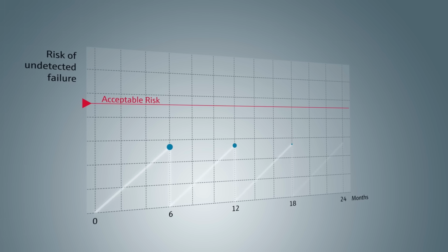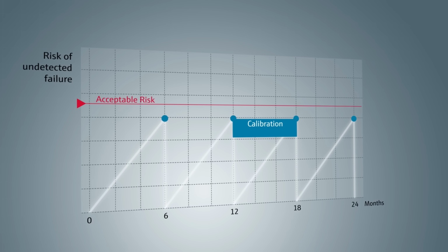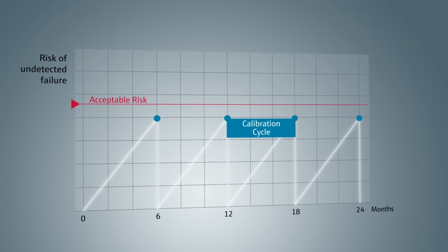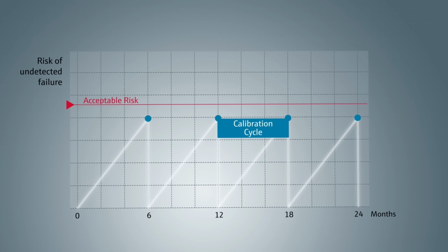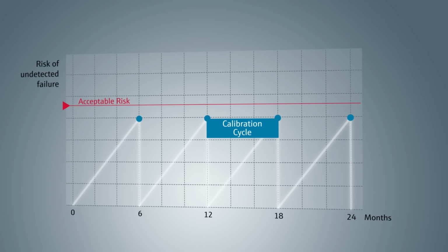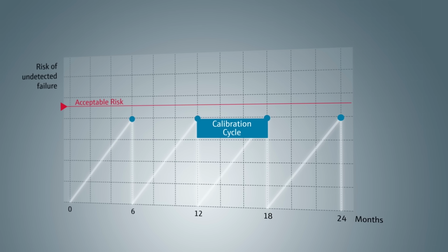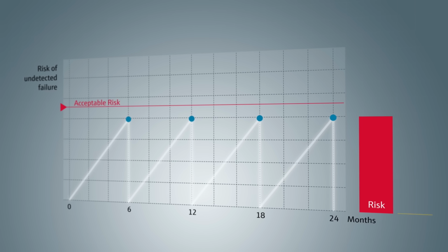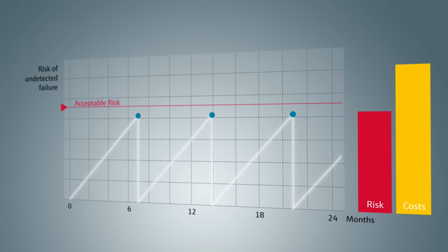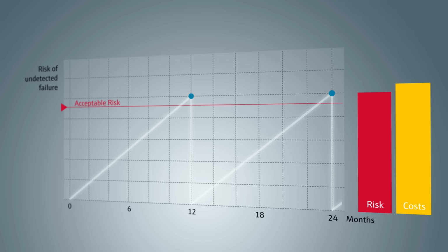All known temperature sensors, including PT100 sensors, are subject to aging effects that can lead to drift. Longer calibration intervals increase the risk of undetected drift. Until now, these intervals have been determined by assessing the acceptable level of risk.